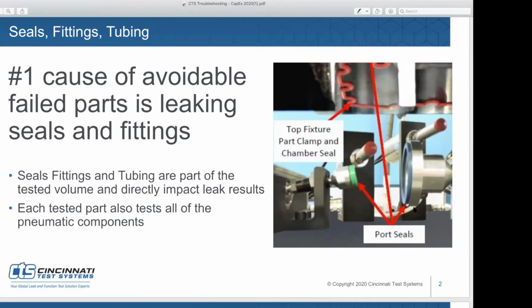It may not bubble all the time. It may just come to a certain pressure and then eventually emit some air pressure from the part. And it's not a constant leak, but it's a form of weakness because of your alignment of your seal. The other thing that will cause that is seal wear. So if you're not compressing it well enough, coming to a positive stop, and it's wearing and your seal is floating from the pressure emitted from the compressed part or from the pressurized part, then you're going to see some seal movement from that standpoint too.